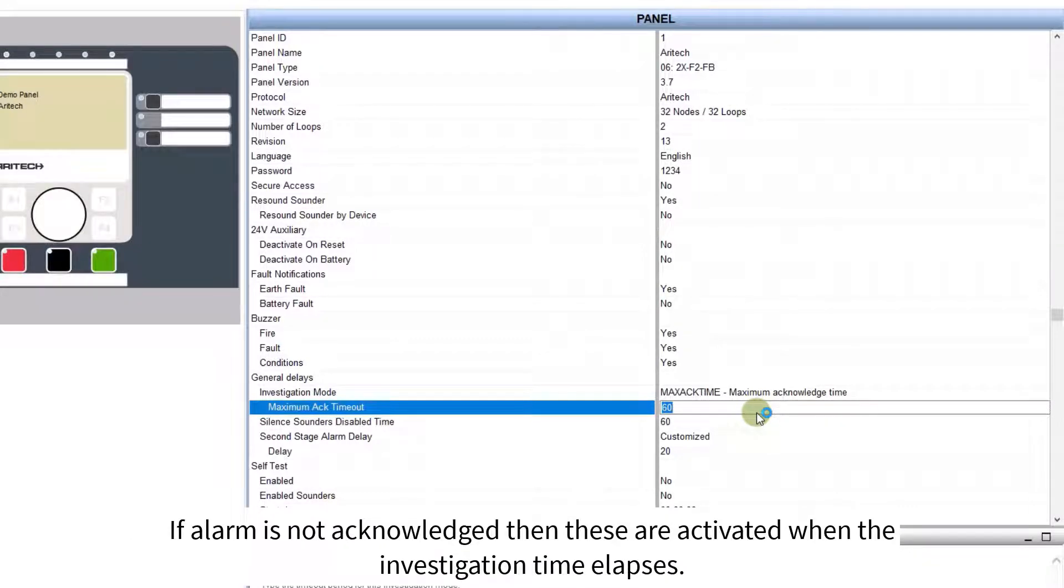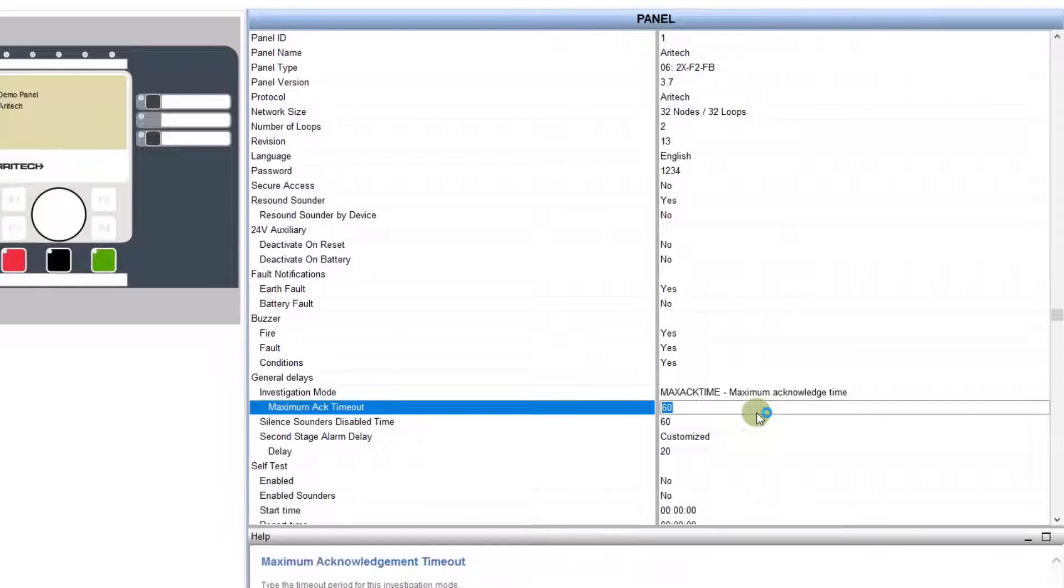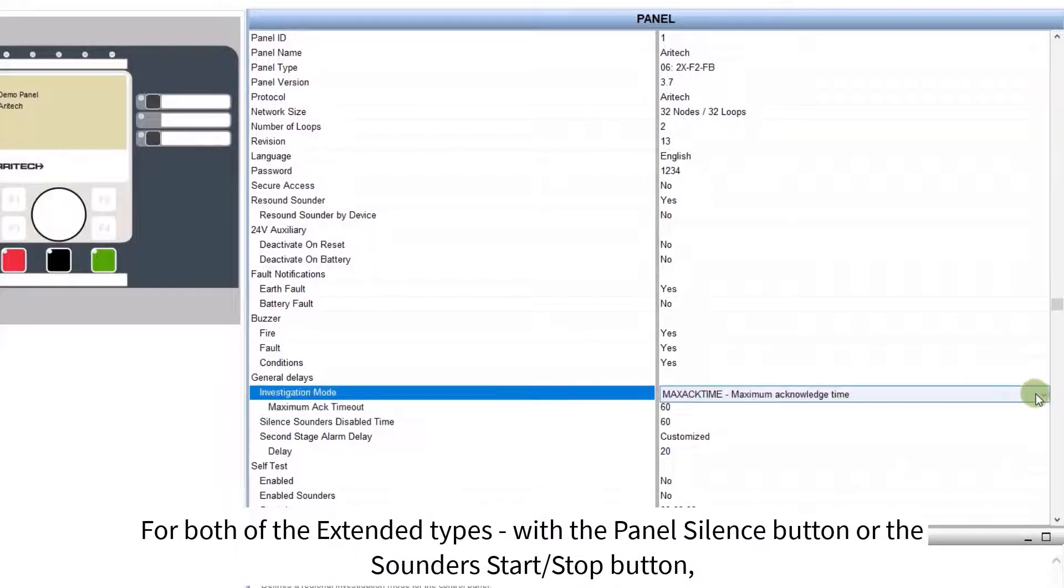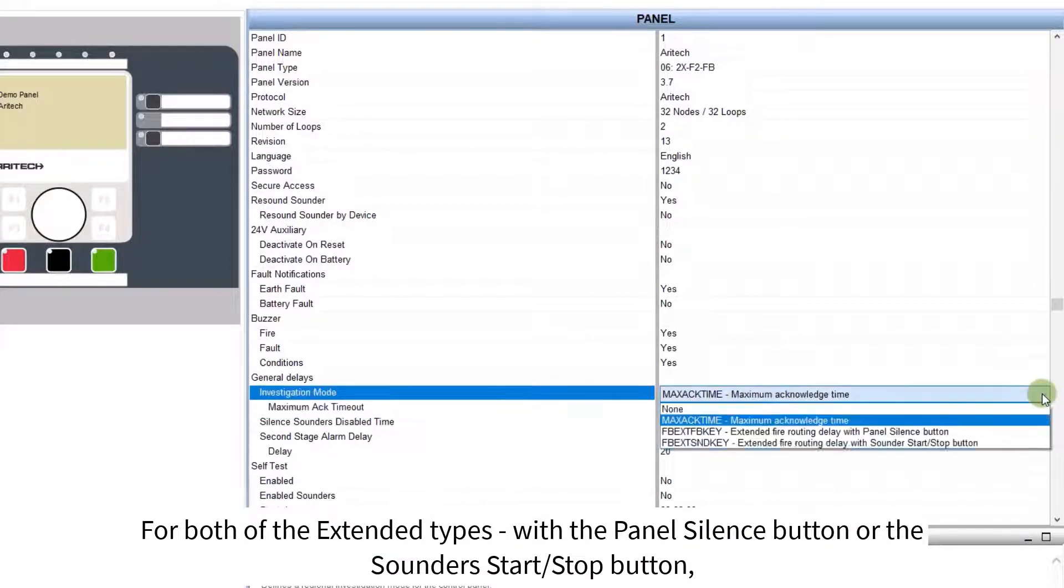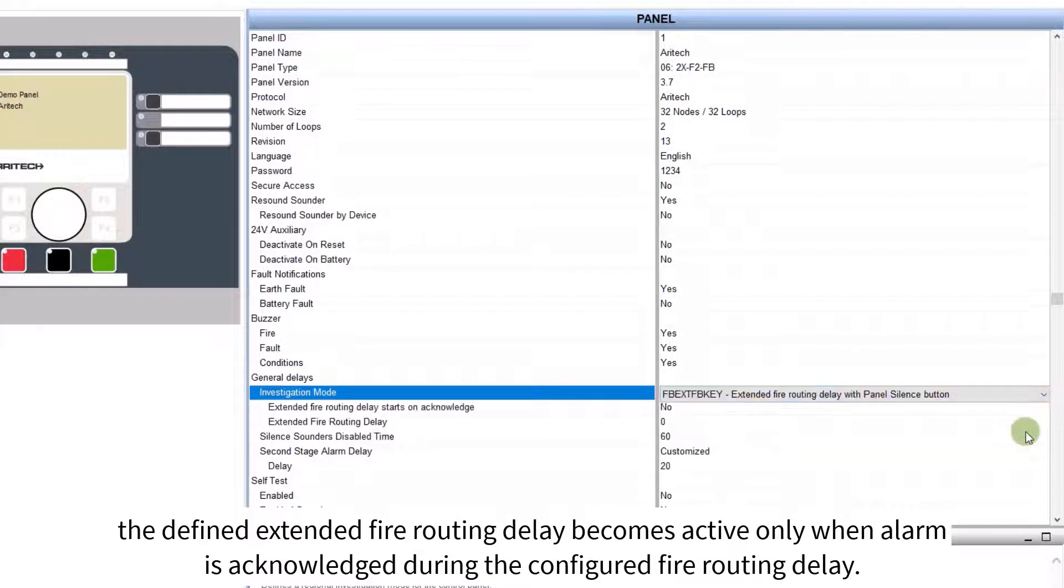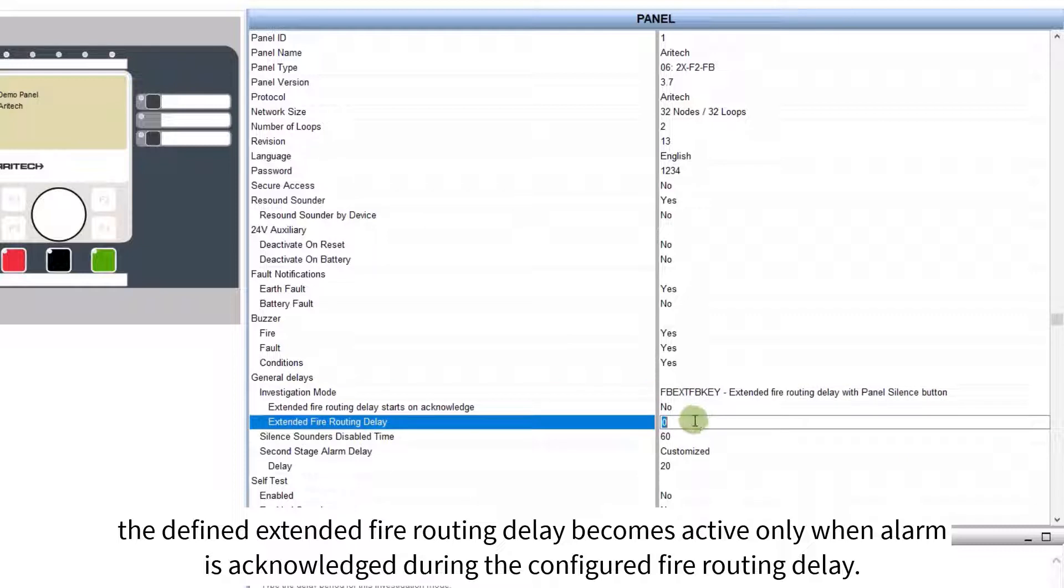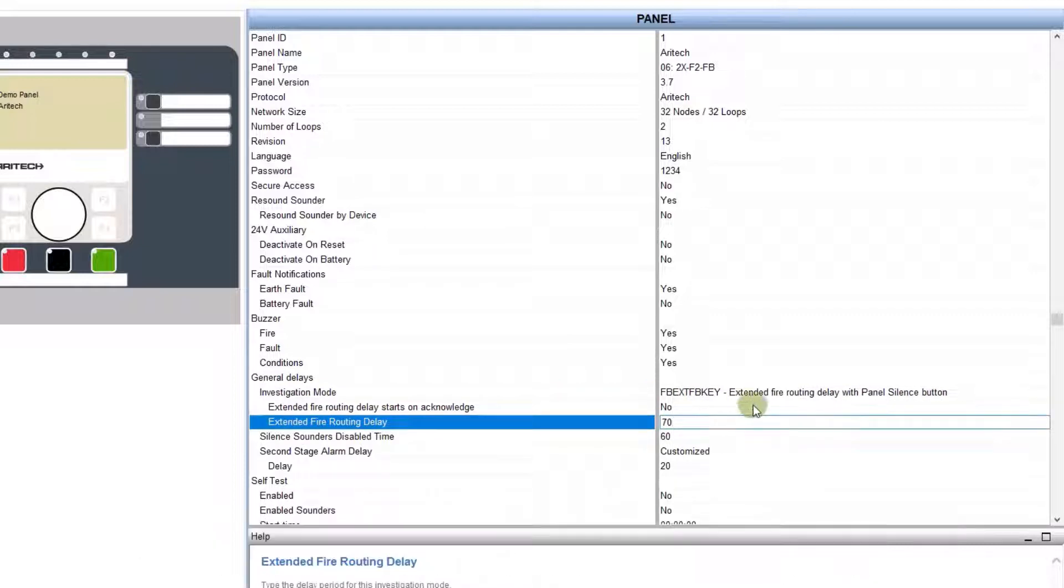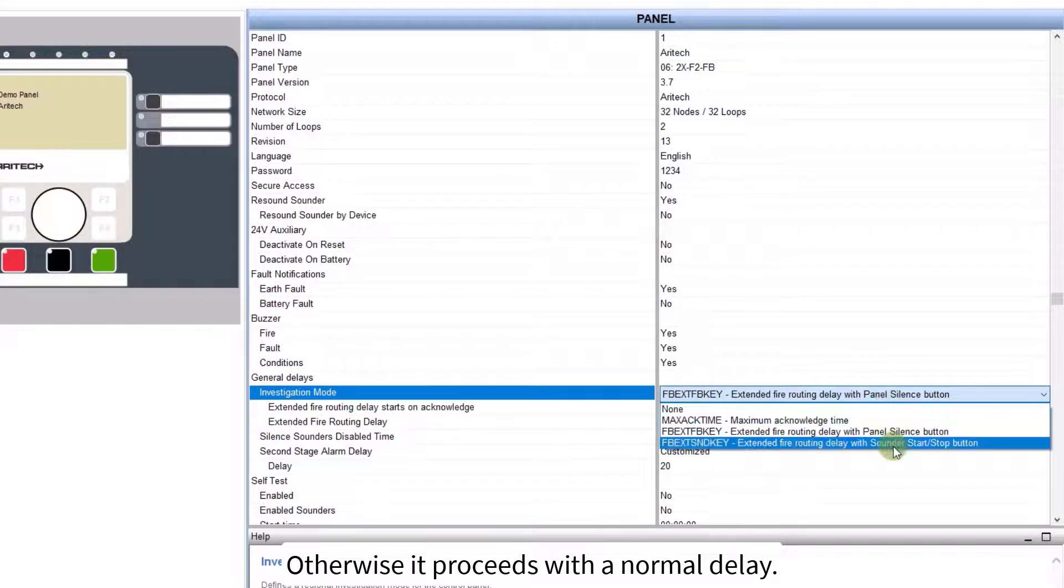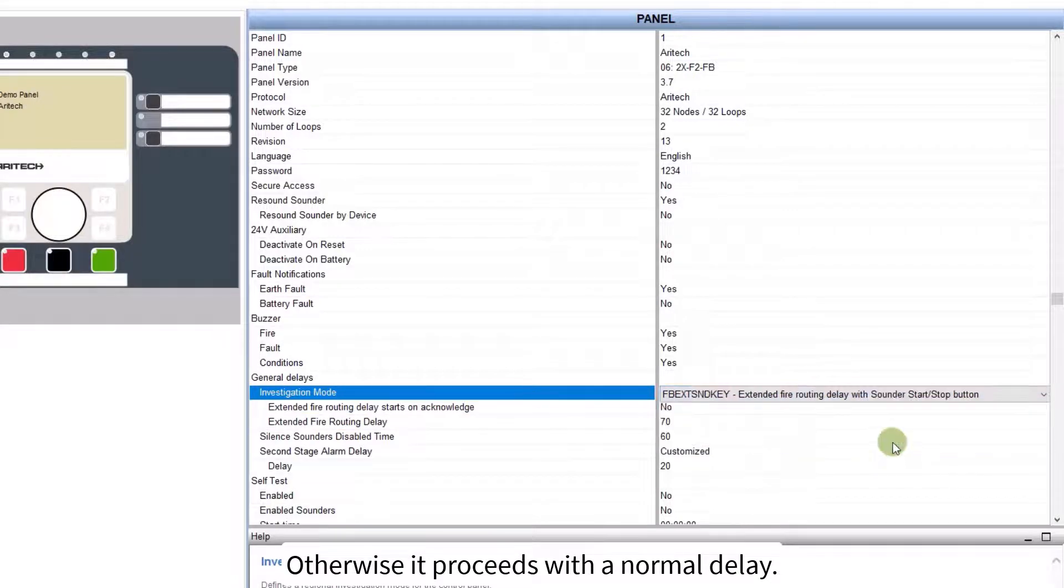For both of the extended types, with the panel silence button or the sounders start stop button, the defined extended fire routing delay becomes active, only when alarm is acknowledged during the configured fire routing delay. Otherwise it proceeds with a normal delay.